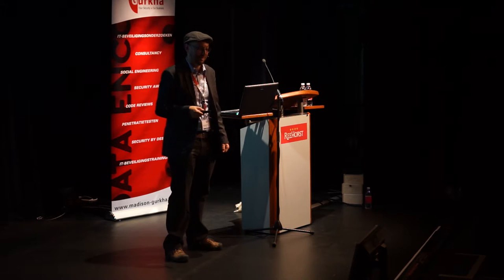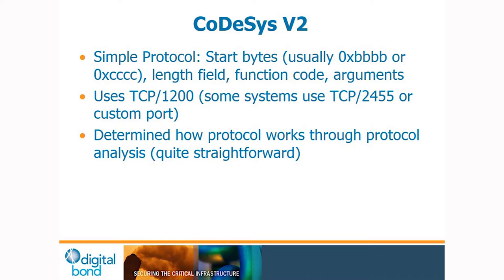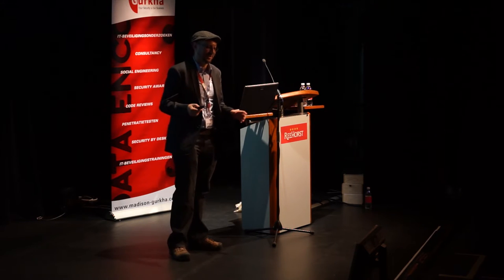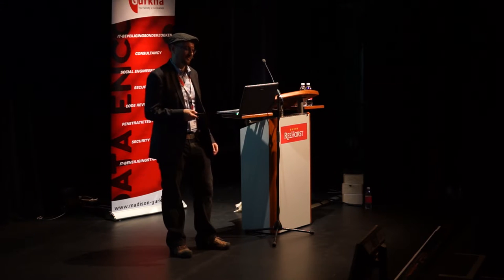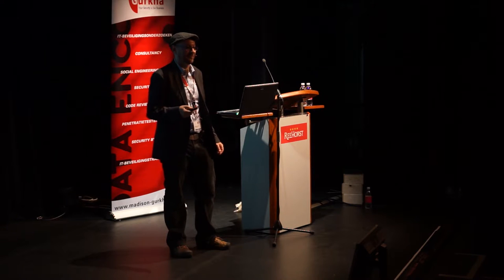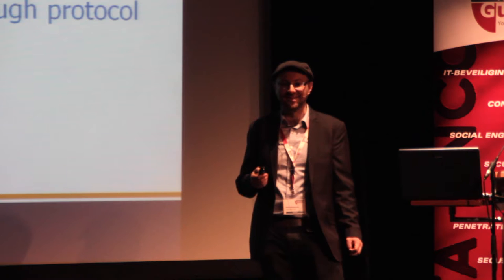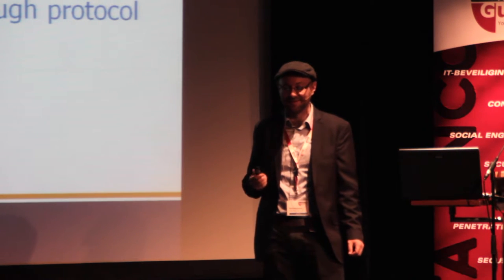For the version 2 protocol, you can download scripts from the Digital Bond website. It has two start bytes — BB BB or CC CC — then a length field. The length field is endian-dependent: little-endian for little-endian controllers, big-endian for big-endian controllers, and you have to tell the PC software which endianness your PLC is. After the length field there's a function code, then arguments. Version 2 usually uses TCP port 1200 or 2455, though some vendors use a custom port. Figuring out how the protocol worked was pretty easy — just analyzing PCAPs and looking for unique packets that correspond to particular commands.